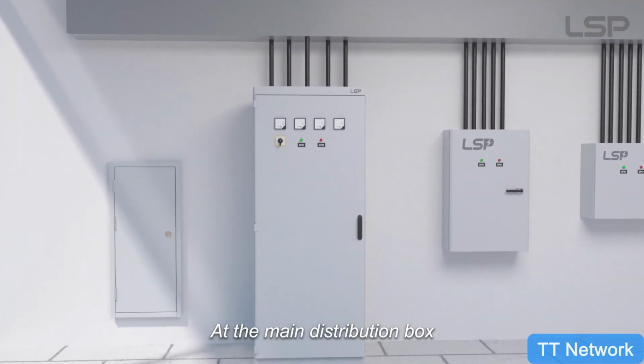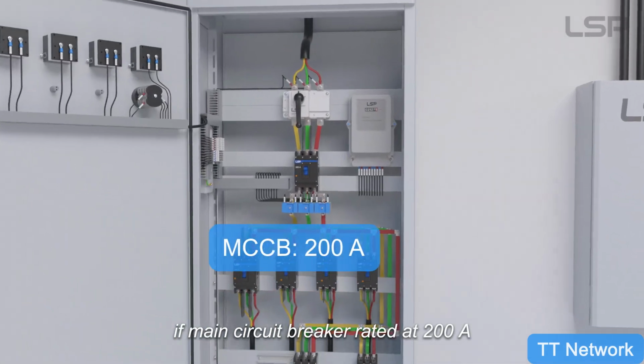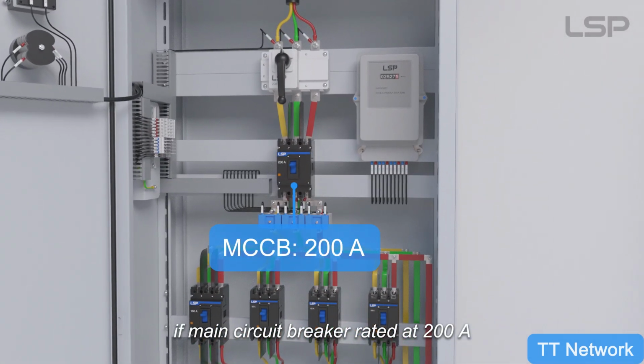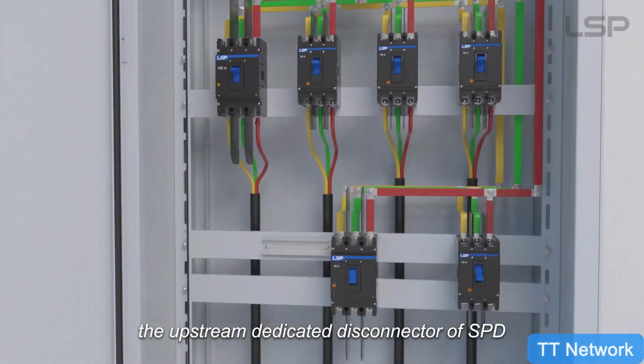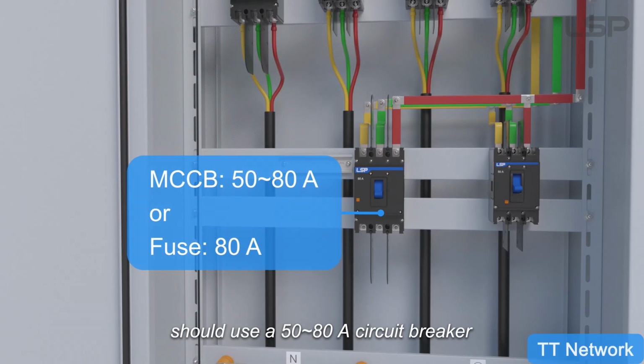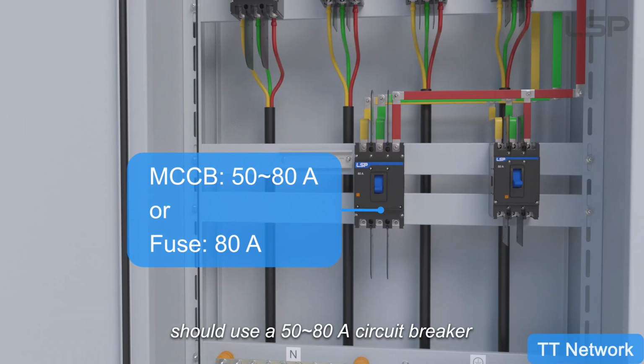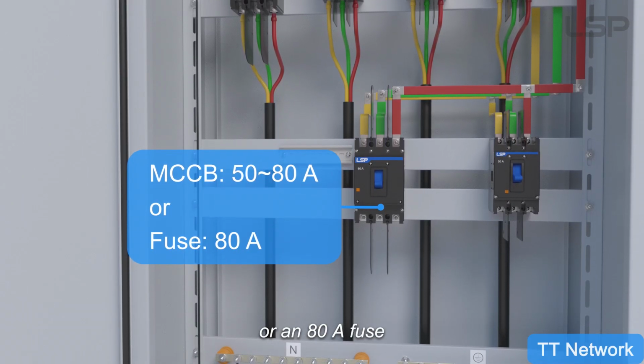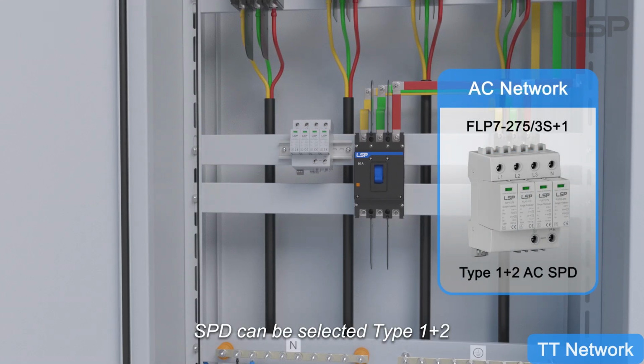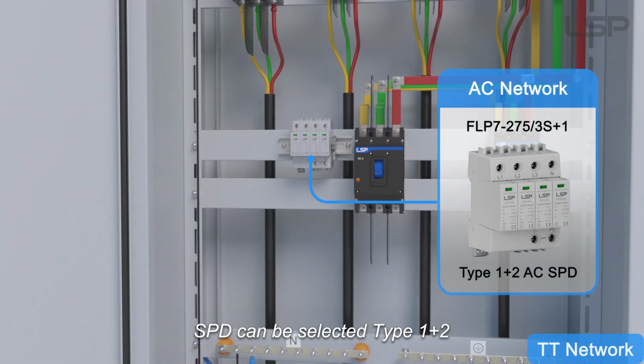At the main distribution box, if the main circuit breaker is rated at 200 amperes, the upstream dedicated disconnector of SPD should use a 50 to 80 ampere circuit breaker or an 80 ampere fuse. SPD can be selected type 1 plus 2.